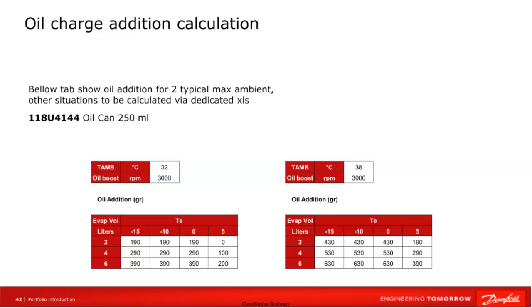It is worth using a dedicated Excel sheet that allows accurate calculations of the maximum refrigerant and oil filling adapted to specific temperature conditions. This allows you to precisely determine how much oil is needed in a given situation.